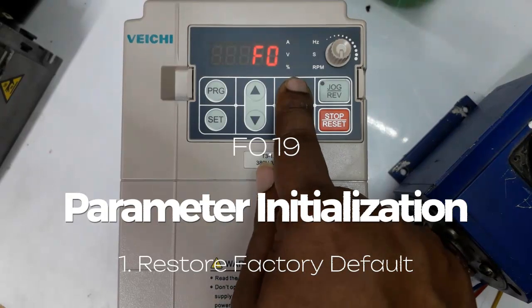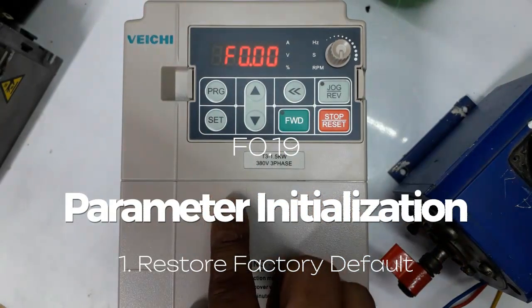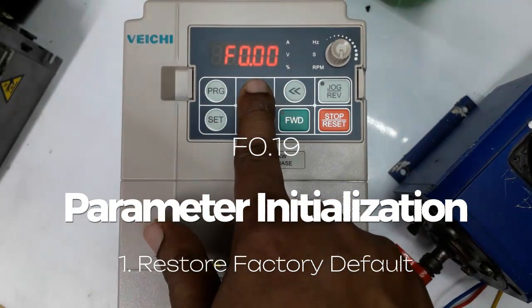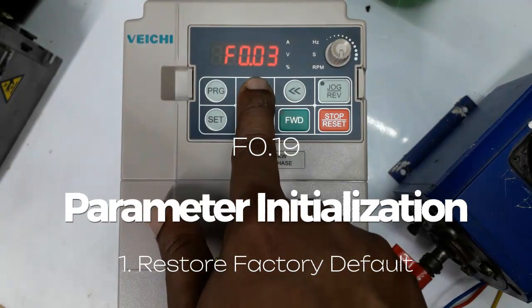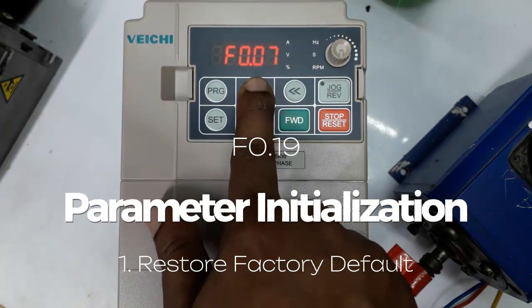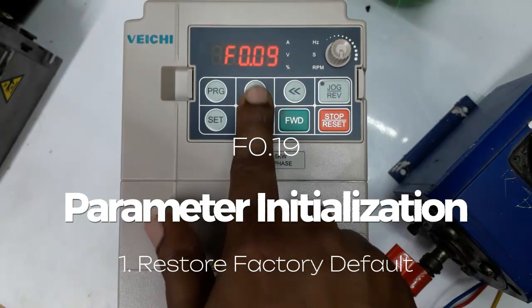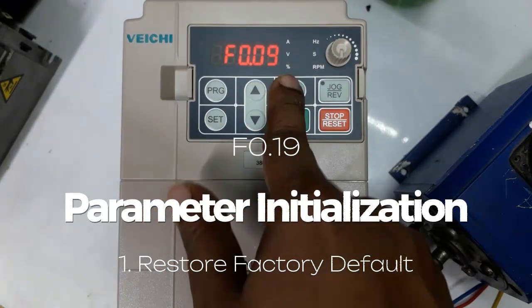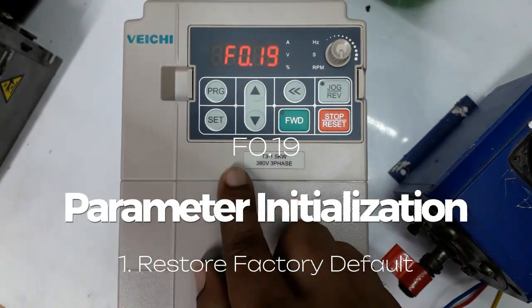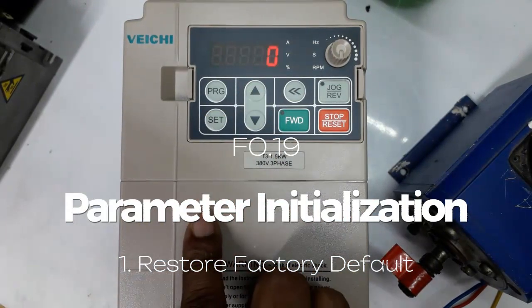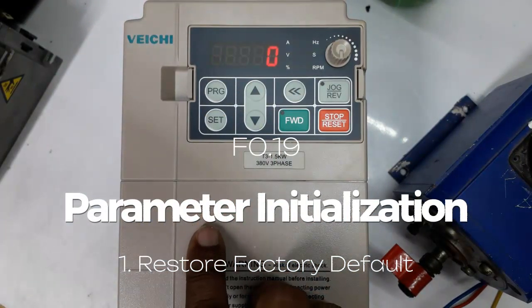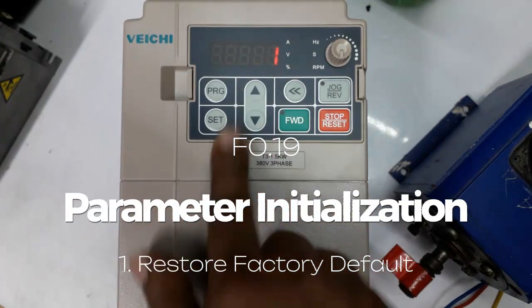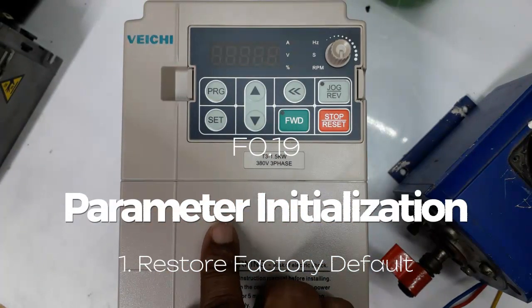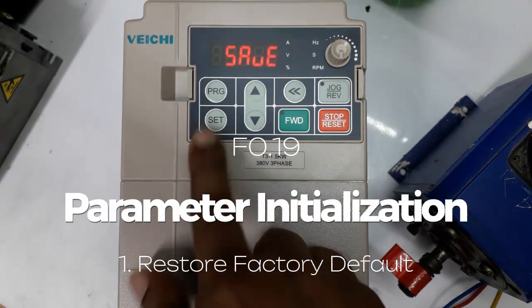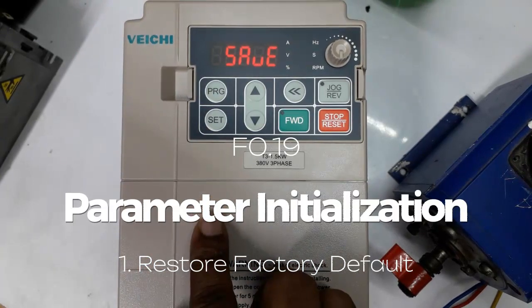Initialize parameter is F0.19. So enter into the parameter F0.19. Here it is showing 0 for no action. We set here 1 for restore factory default parameter. So set and save to initialize the drive.